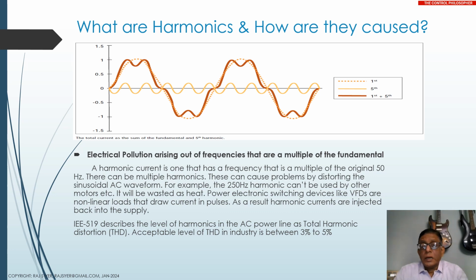However, there are standards to regulate these things so that the harmonics are well within acceptable limits. The acceptable content of harmonics in the power supply to a drive is only about 3%. Some customers allow it to be 5%. But yes, they are there. If we have to take action, harmonics will be induced if the cable connecting the VFD to its motor is very long. You should be particularly careful if there are residential areas in the vicinity of an industry which has a large number of high power drives.